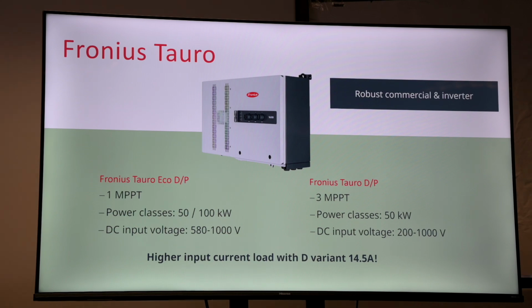And then on the standard, so the Fronius Tauro P and D, this is referring to the 3 MPPT input grid tie inverter, but it is only available in the power class of 50 kilowatts. And again, your DC input volts do change depending on what unit you are ordering. So if it's the Eco, it's the 580 to 1000 volt DC input, whereas the standard is 200 to 1000.